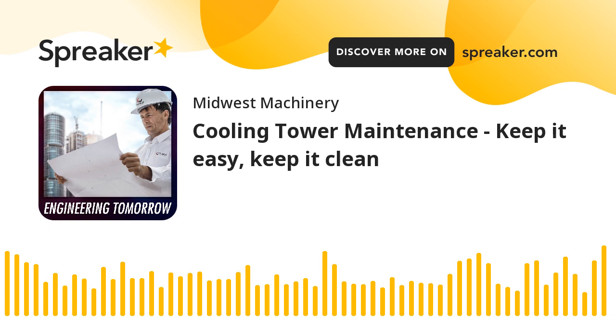Another thing you can do is make sure you maintain your water level. There's going to be a recommended water level line on every tower. By maintaining that, you'll have a surface velocity that helps sweep all your dirt and debris in your basin down into your drain, so you won't have buildup if you maintain that recommended level. You don't want it too low because that causes problems on your pump, and you don't want it too high because then you won't have that surface velocity you need. So that's something you really need to look out for, whether by adjusting a float valve or any other water level control you have. Definitely something you need to be monitoring closely.